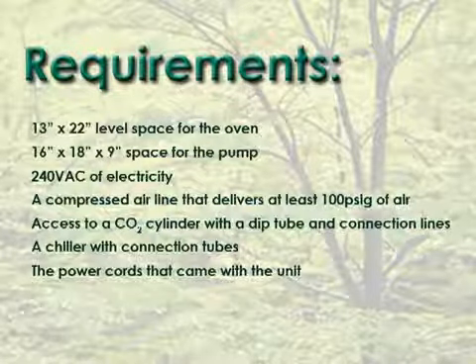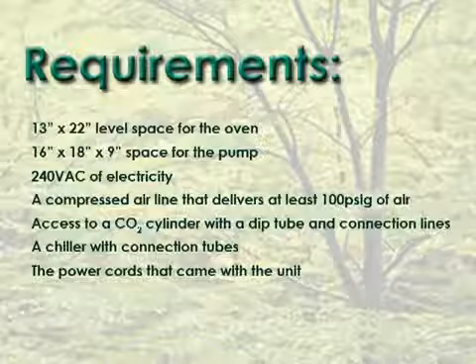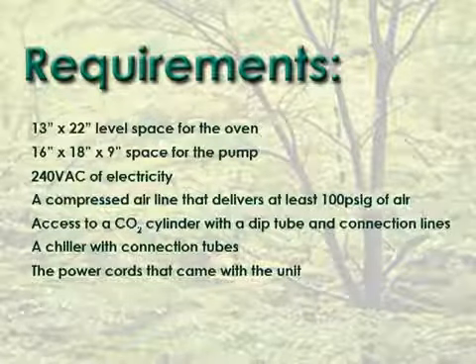In addition, the system requires 240 VAC of electricity, a compressed air line that delivers at least 100 PSIG of air, access to a CO2 cylinder with a dip tube and connection lines, a chiller with connection tubes, and the power cords that came with the unit.